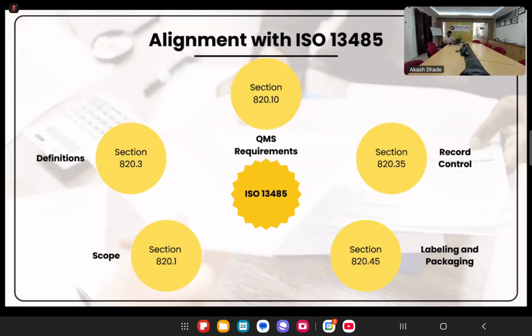Now this section 820.10 talks majorly about QMS requirements. Okay. Now in ISO 13485, the QMS requirements are given from clause number 4 till clause number 8, which talks about management responsibility, then production capabilities, continuous monitoring. All these requirements are also given in alignment with QMSR. But there are requirements such as medical device reporting, identification and traceability, as well as unique device identifier. These are some of the requirements which were already there in QSR. Those are taken as such in QMSR, but you should have SOPs, standard operating procedures, for following all these concepts.